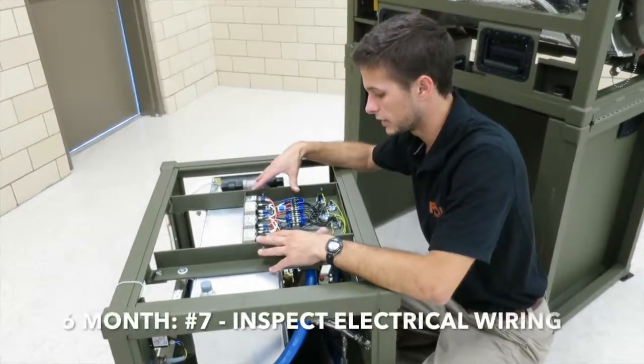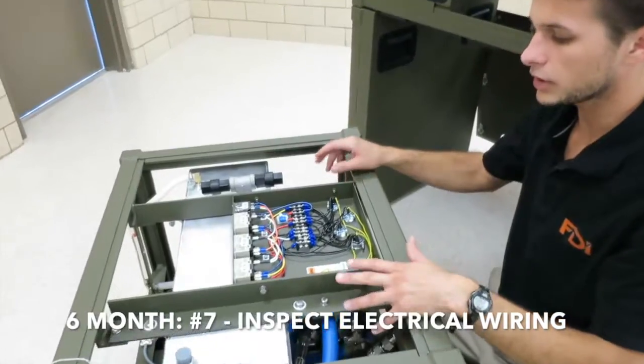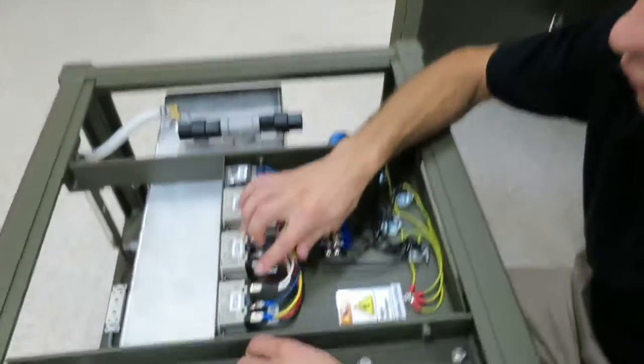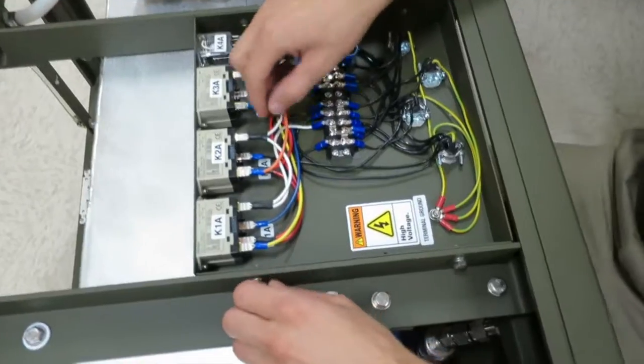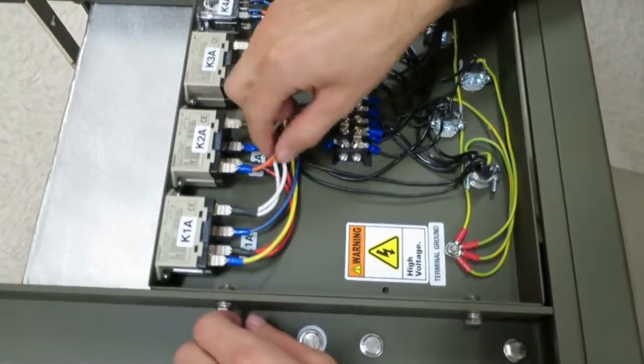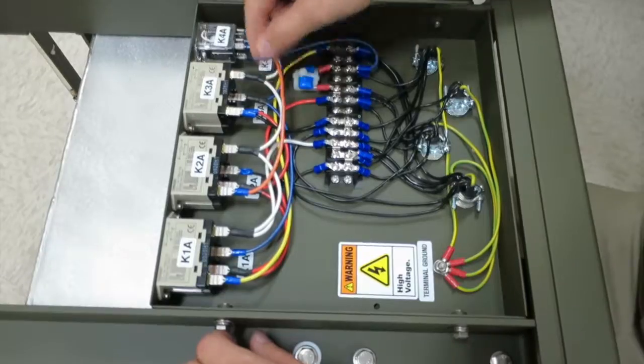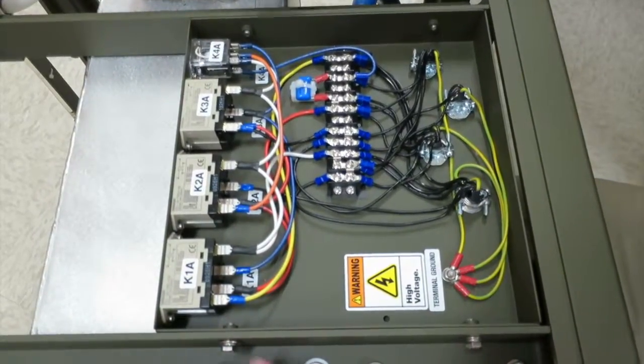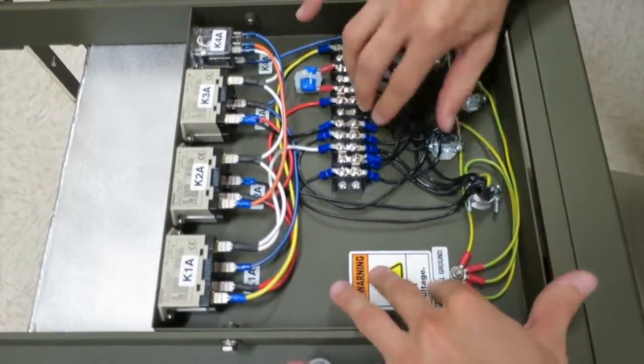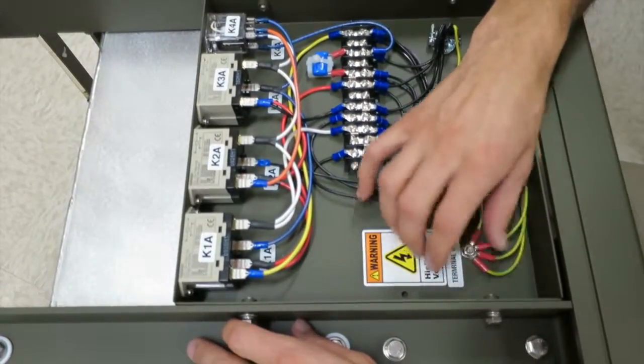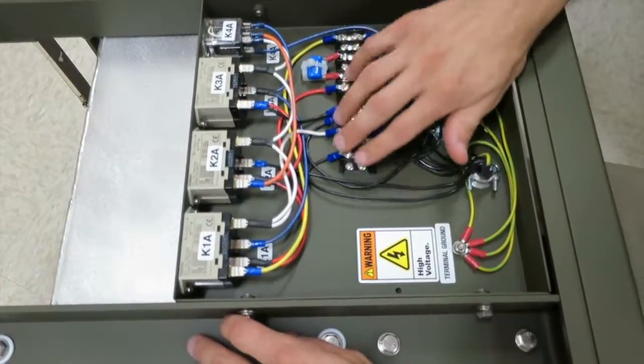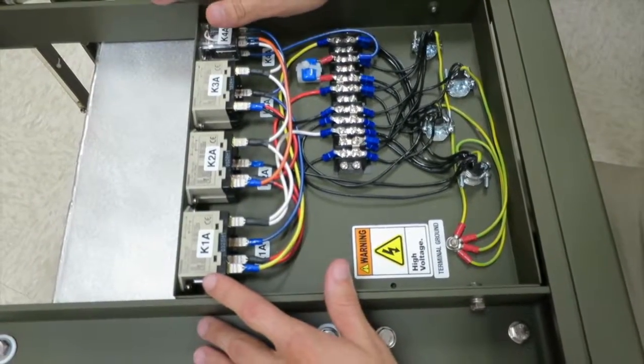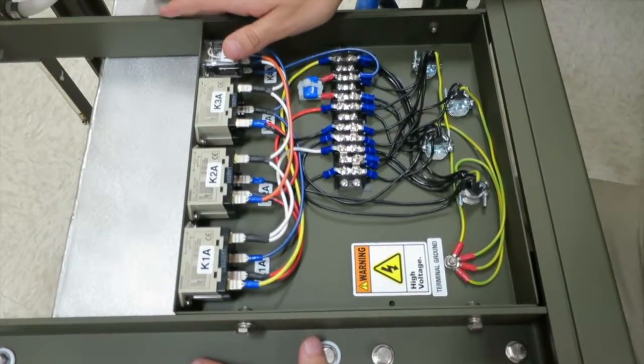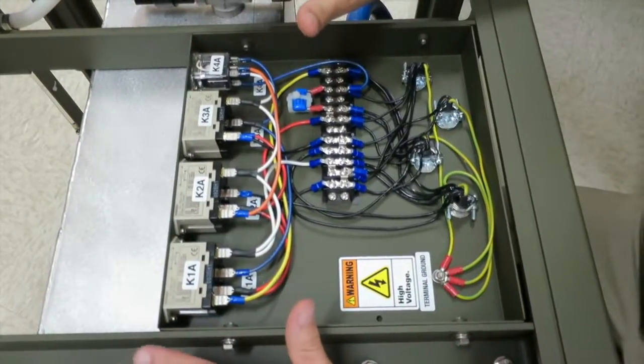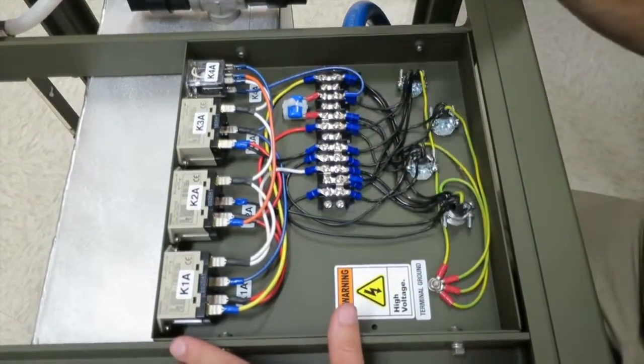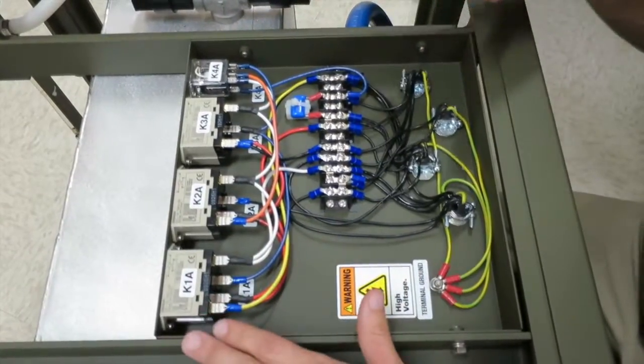So if you zoom in here close, you're just going to want to look for any corrosion on the connectors. You're going to want to look for any loose wires. You can do a gentle tug and they should all be firmly attached. Also look for loose metal objects, dirt, anything that can rattle around and possibly short circuit this terminal board here. As always, please be safe about it and make sure you're de-energized and completely disconnected before you remove this panel to inspect all these wires.